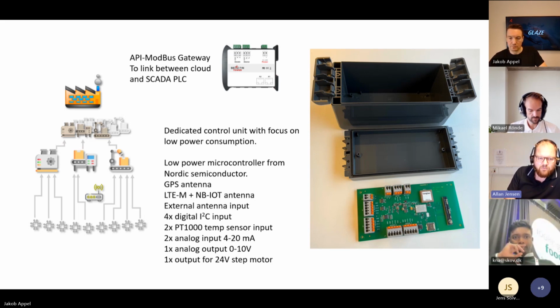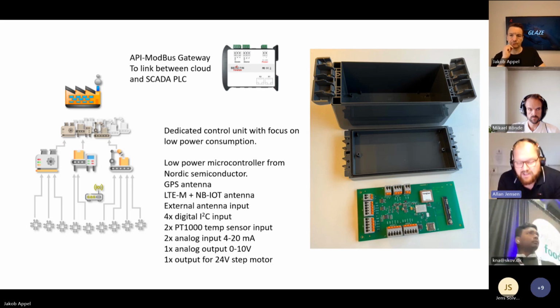And it's working by LTE-M, narrowband IoT. There's a built-in antenna, and there's also an external antenna, so we can take the antenna outside of a well. We have 4 digital I2C inputs. We are using them for the pressure transmitters, which are also digital, and by that have low power consumption. And we have 2 analog inputs, 4 to 20 milliamps, and 1 analog output, 0 to 10 volts, so we can control other motors. And we have output for a 24 volts step motor.